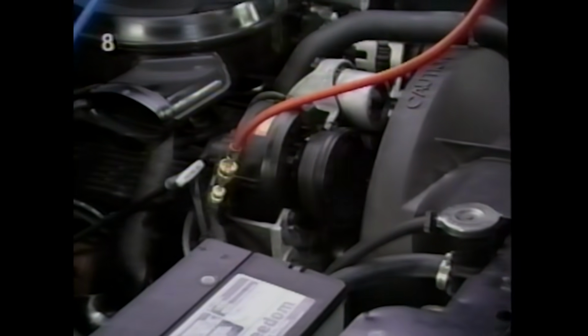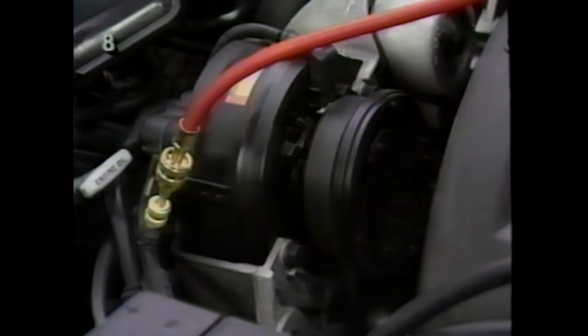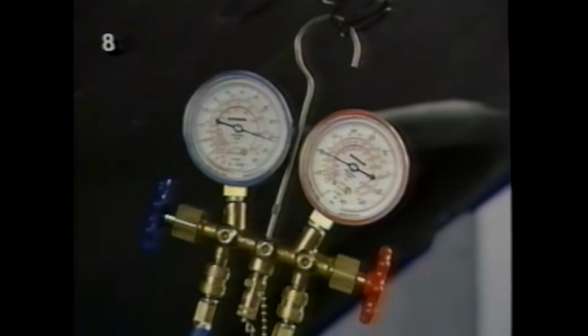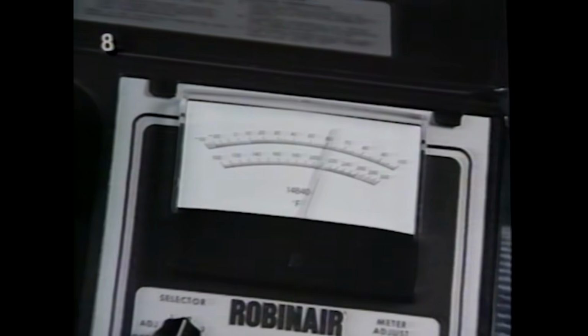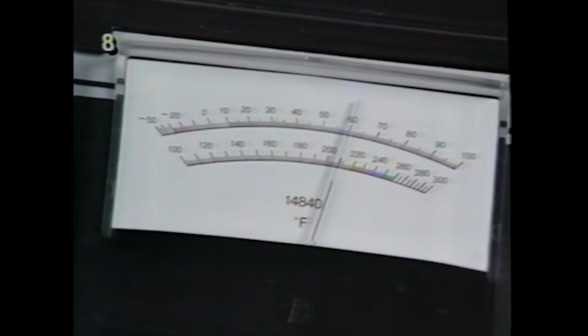Remember that the clutch should disengage around 25 psi to prevent evaporator freeze-up. The actual range specified is 20 to 28 psi, and it should engage within the range of 41 to 51 psi. With a cycling pressure switch that isn't cycling properly, recovery of the R12 is not necessary to replace the switch. The pressure switch fitting on the accumulator has a Schrader-type valve. One last point worth mentioning is that the refrigerant pressures will equalize through the orifice tube when the system is shut off. That's all for now, and as the saying goes, keep cool.